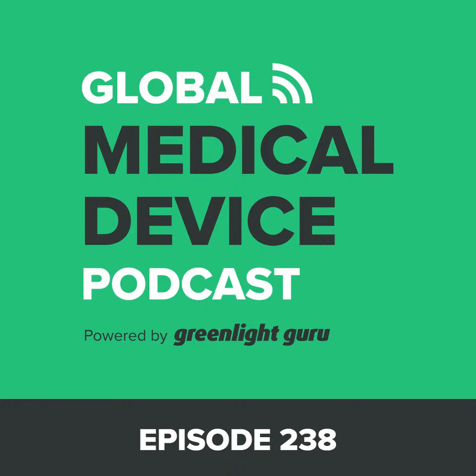There's a lot of areas. I could give you a number of examples where FDA used its enforcement discretion for a while, and then somebody did something that they probably shouldn't have done, and boom, everything changed. What I'm saying to companies now is go ahead and develop your product and put it out there on the market, but make sure you do all that other stuff, like the V&V, like the usability testing and so on, so that if and when it does change, and FDA says, oh, no, you now need a 510(k) to do what you're doing, it's just a matter of taking all that information that you've already done, putting it into a package, stamping 510(k) on the front and sending it to the FDA, and you're done.